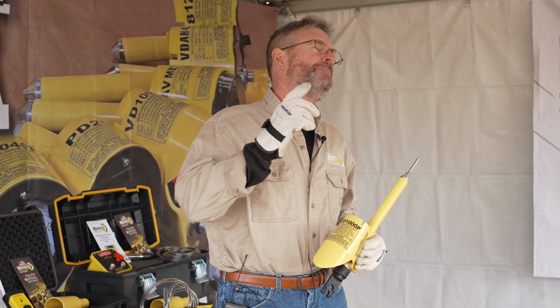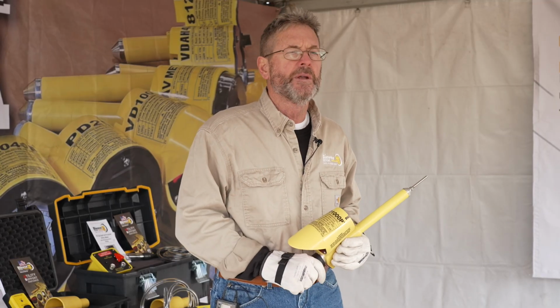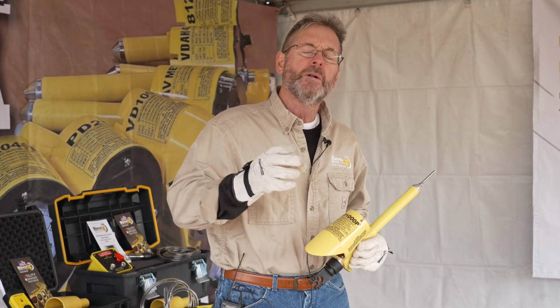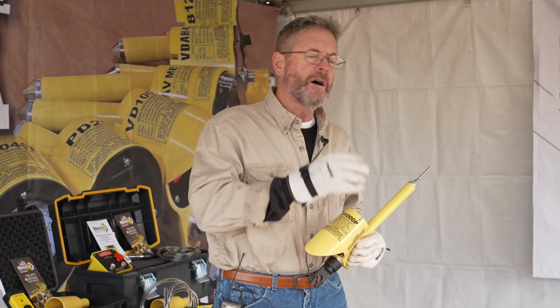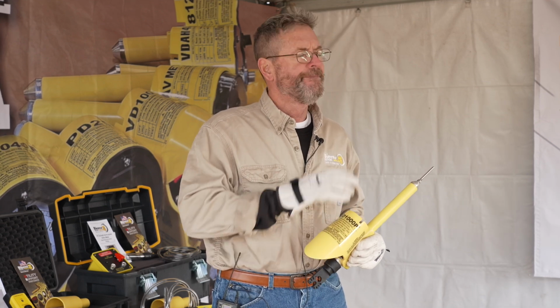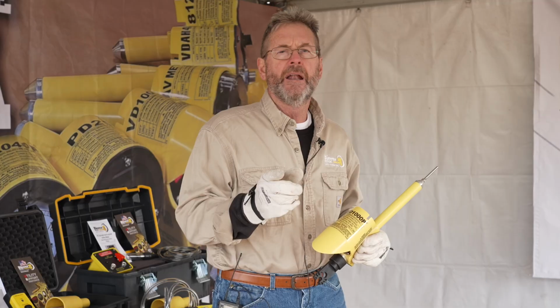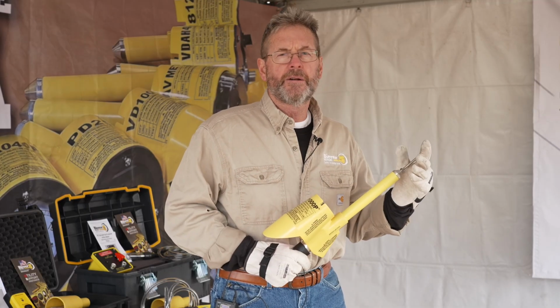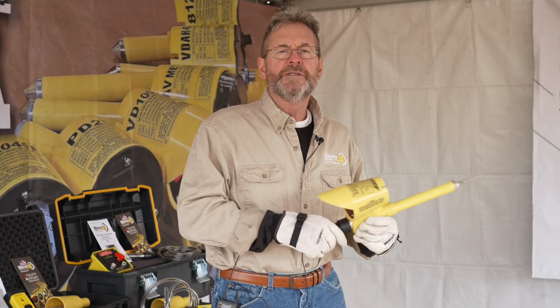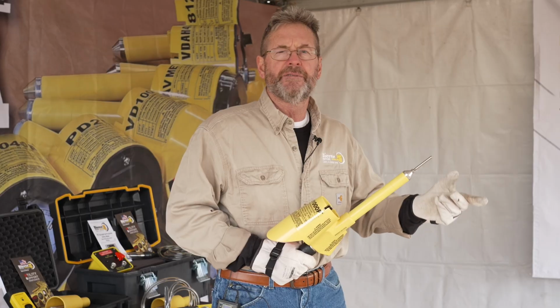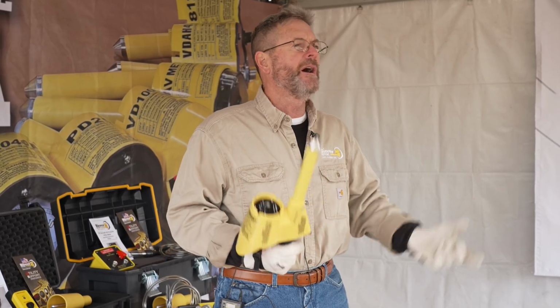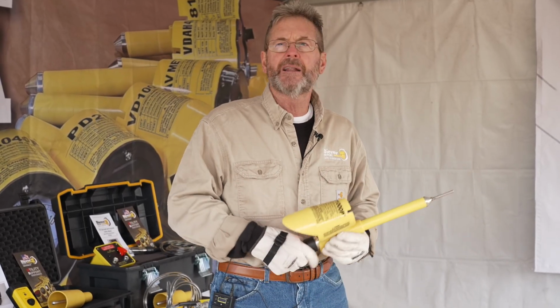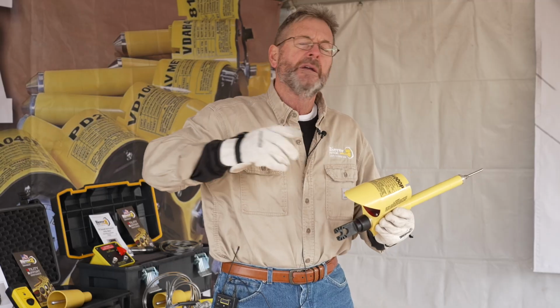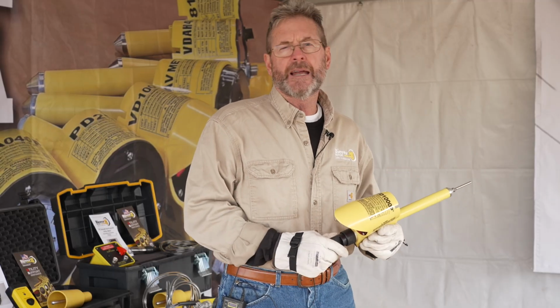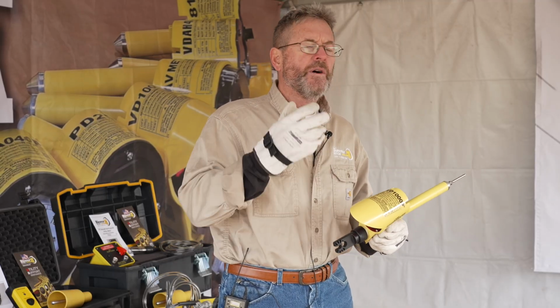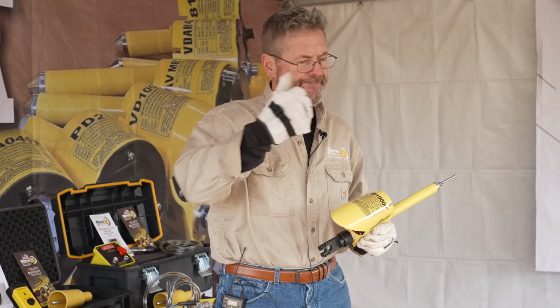This is one of the biggest things we see out in the field, that a lot of folks are still using non-contact voltage indicators. No, we're not going to do that, we're going to use direct contact. We do not want that tool to give you a false positive or false negative. If you're on an underbuild, in a substation, or have a lot of conductors close by, don't use the non-contact tools. Thankfully, folks are making the change.